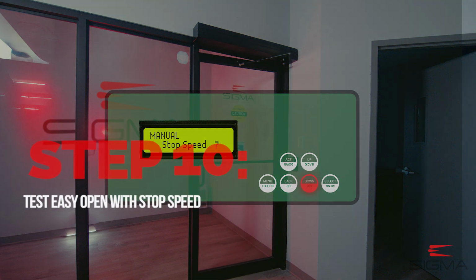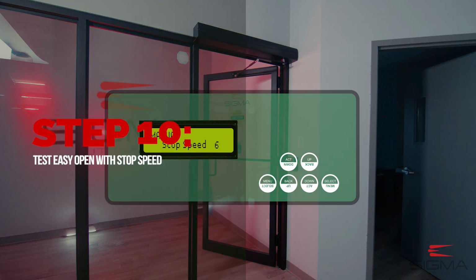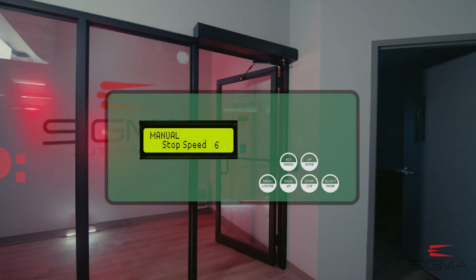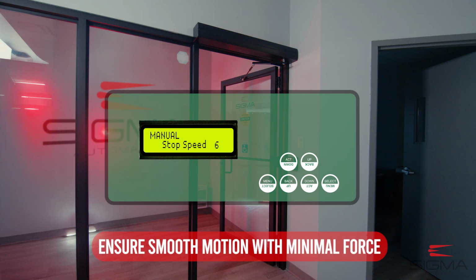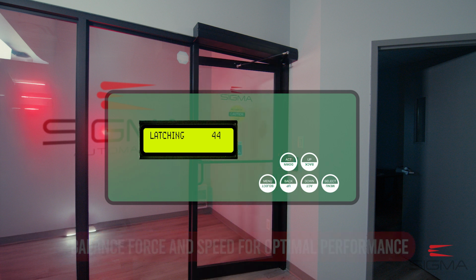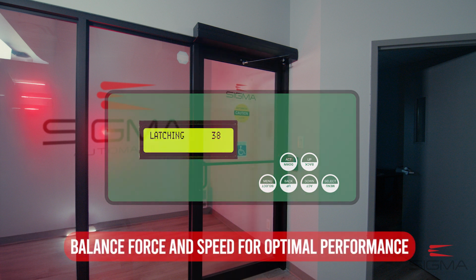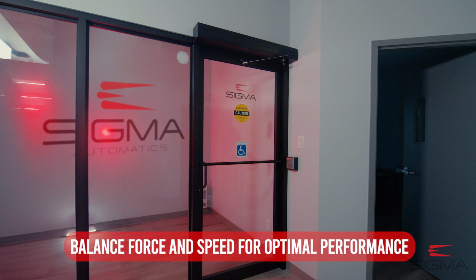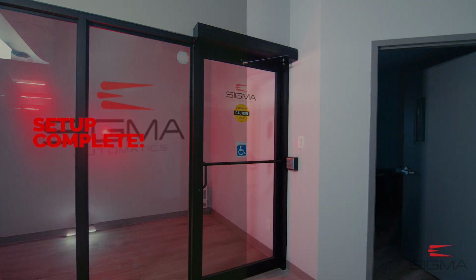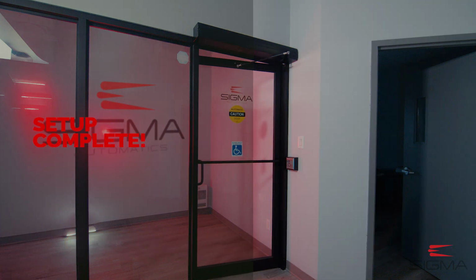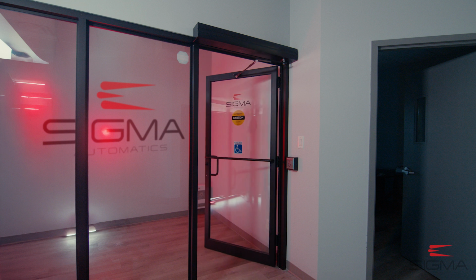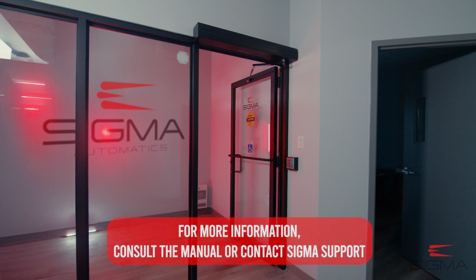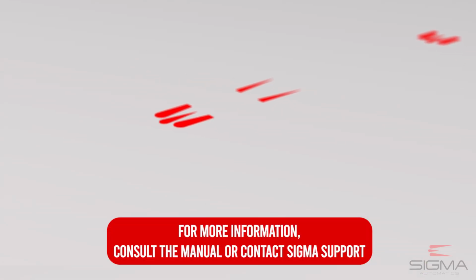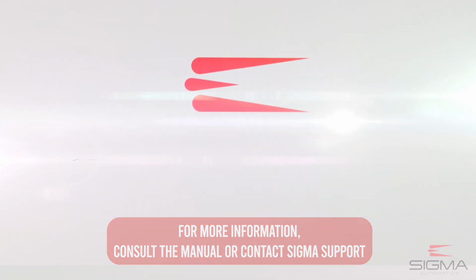With Easy Open enabled, a 12-foot heavy glass door can be set in motion with just 5 pounds of force. Adjusting the stop speed ensures the door closes smoothly and safely, providing the right balance between force and speed. With these basic setup tips and troubleshooting steps, your SA300 automatic door operator should perform efficiently and safely. For further details on advanced settings, consult the operator's manual.